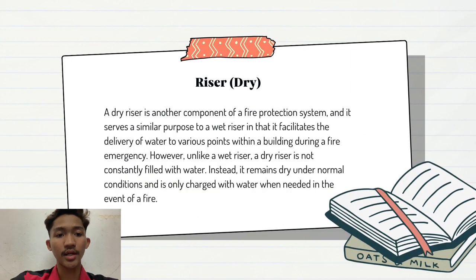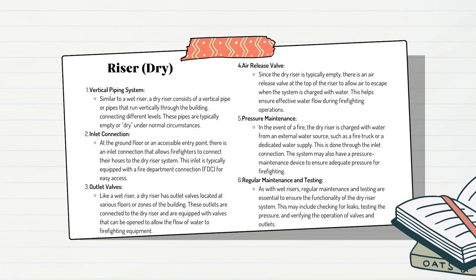Dry riser. A dry riser is another component of a fire protection system, and it serves a similar purpose to a wet riser in that it facilitates the delivery of water to various points within a building during a fire emergency. However, unlike a wet riser, a dry riser is not constantly filled with water. Instead, it remains dry under normal conditions and is only charged with water when needed in the event of a fire.